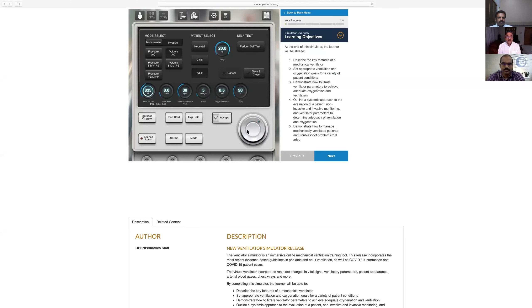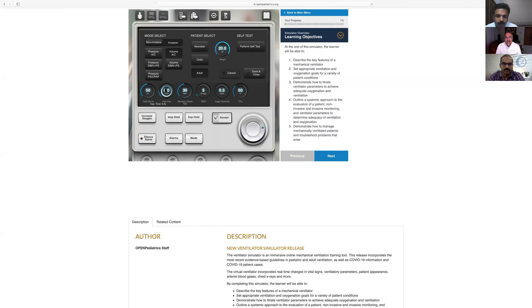You have a direct setting of tidal volume. Peak flow — most ventilators by default set the peak flow once you set the tidal volume.